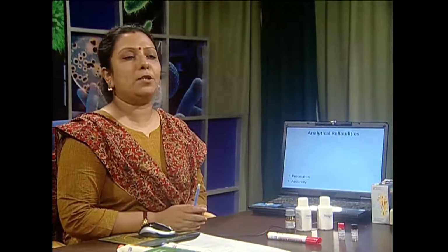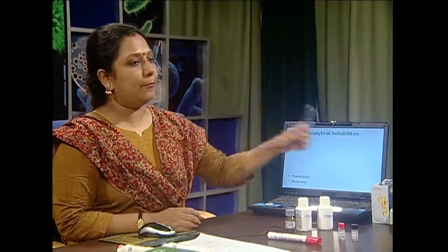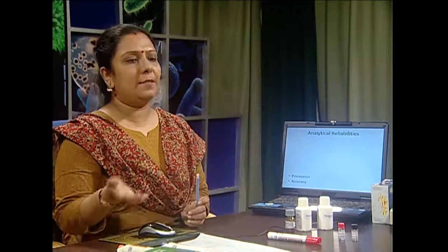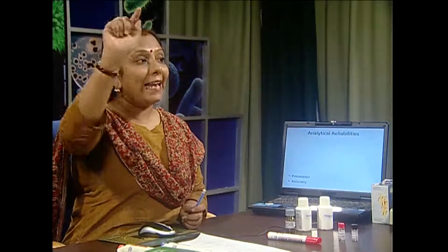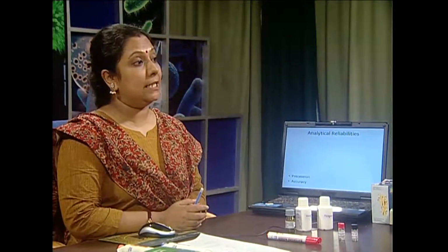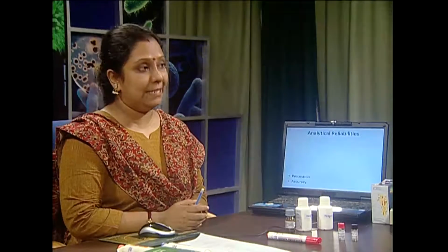It includes the precision as well as accuracy. Precision includes the quality control with respect to commercially available bilirubin that is marketed. We have to calibrate the machine. It can be available in Boehringer, Mannheim and in different companies. And the accuracy must be taken with respect to linear regression analysis. The straight line, the linearity must be maintained up to 20 milligram per deciliter.